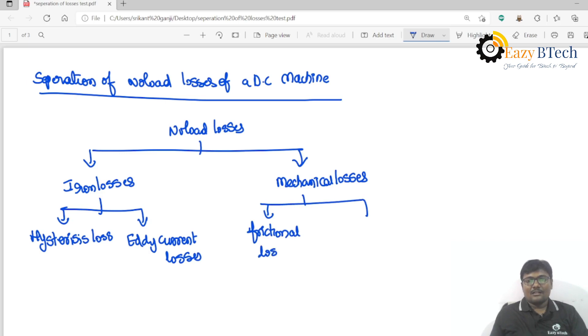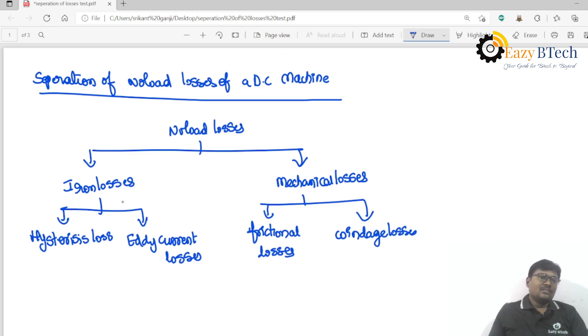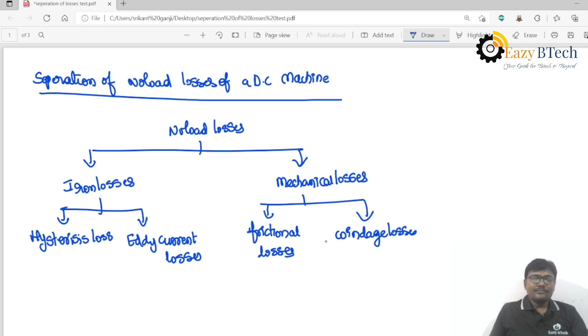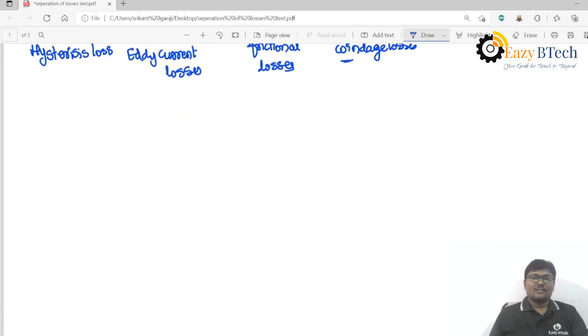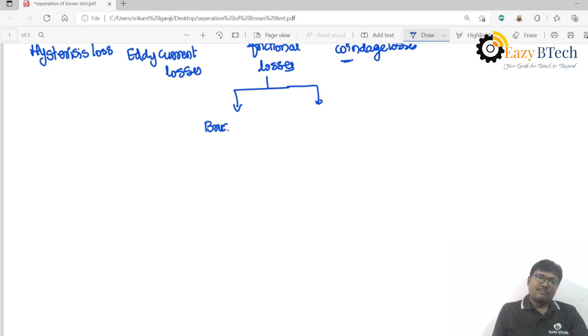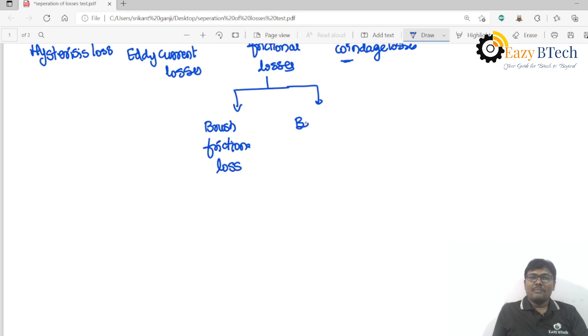Mechanical losses are divided into frictional losses and windage losses. Friction losses arise because the motor has inertia; to overcome that inertia some power is required, so that power is called friction loss. During running, the wind opposition also requires power to overcome — that is called windage loss. Friction loss is further divided into brush friction loss and bearing friction loss.